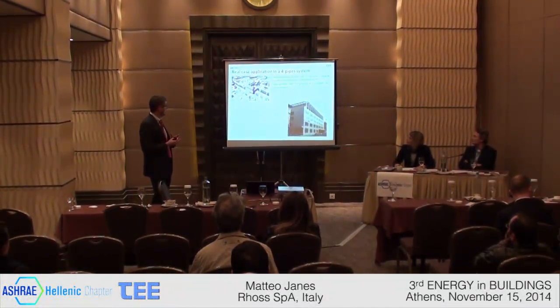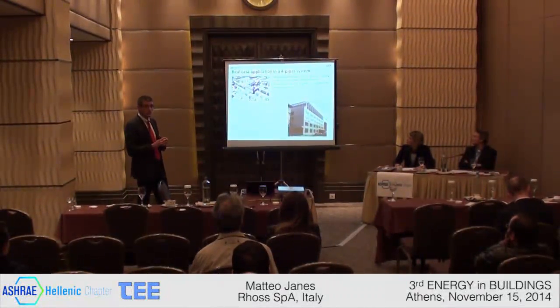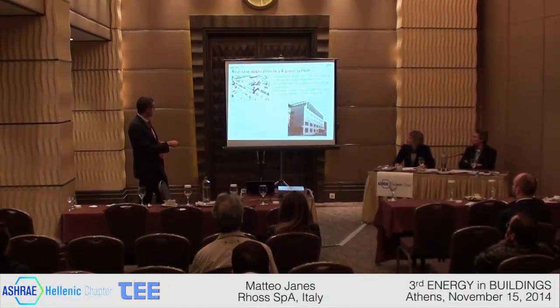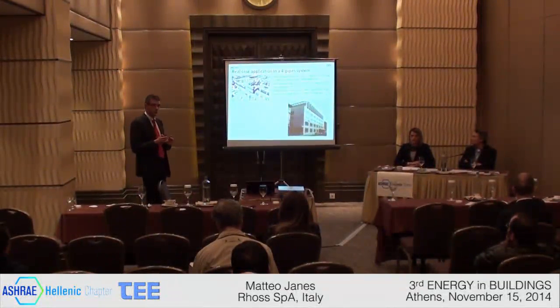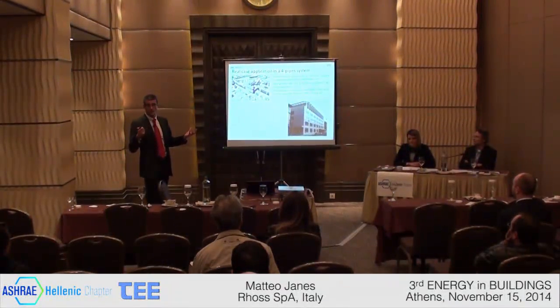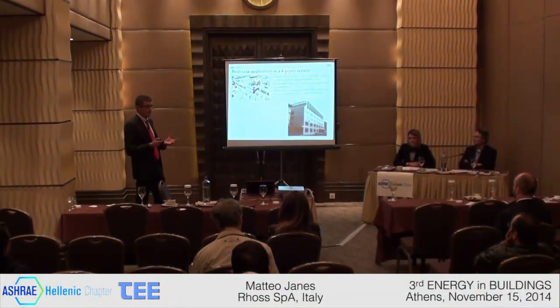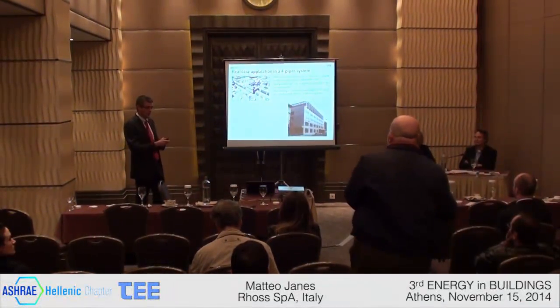The building was enlarged from 4 to 6 stories, and the layout of the building was completely renovated. The investors wanted to achieve the LEED certification, gold level, according to the LEED Guide, Building Design and Construction version 3 of 2009. One opportunity to achieve this certification was to replace the existing HVAC system made by a chiller and a boiler with a polyvalent system, using only a polyvalent heat pump for cooling and heating.